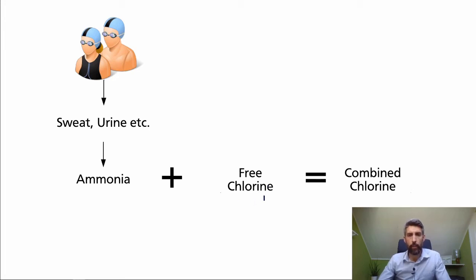There's a key difference between free chlorine and combined chlorine. Combined chlorine is essentially a byproduct, a waste product. It's not really effective as a disinfectant anymore. And in fact, it's more of a pollutant than a disinfectant. Free chlorine is the disinfectant. That's what we want to establish a residual of, whilst at the same time making sure that we're controlling the combined chlorine. So we're trying to minimize combined chlorine as much as we can.